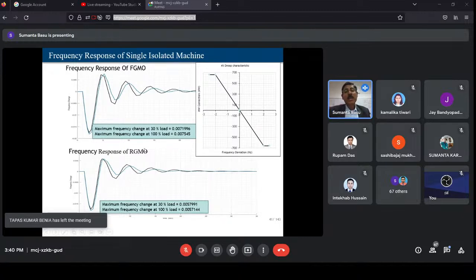And if it is a machine on restricted governor mode with a dead band, you see that the peak frequency is still much lesser compared to without dead band, and the balance characteristics remain the same. So this is an isolated machine, meaning the machine is the only one.